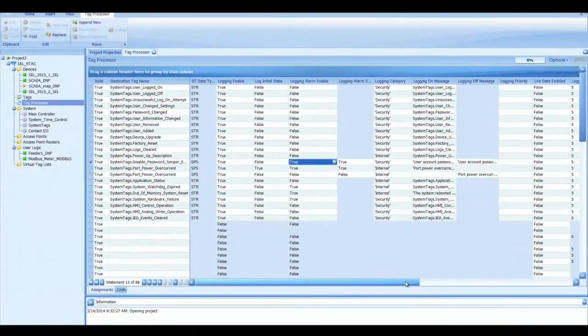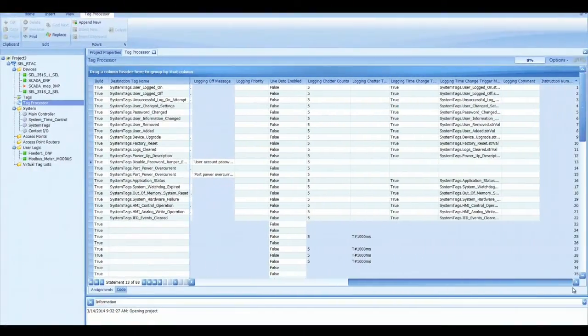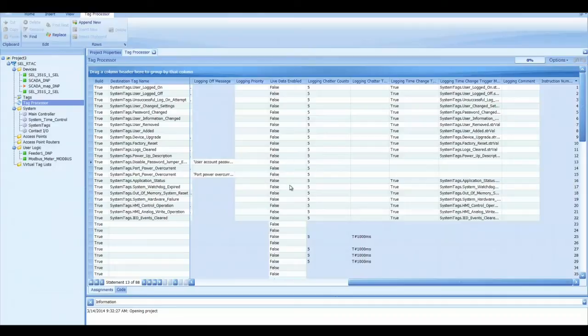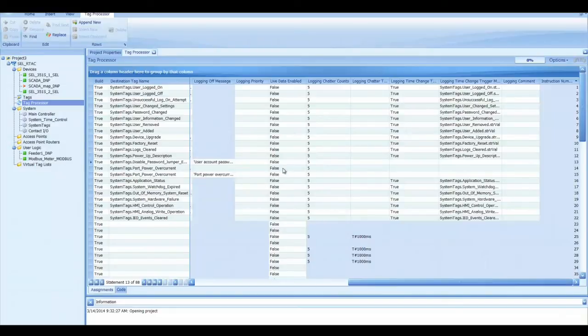Let's scroll over here. Logging priority, that's just a string that you can make up and then you can sort by that priority later. Live data enable is a really cool feature. Any tag that you have configured in the destination tag name, if you turn the live data enable set to true, then it will display that live data on the RTAC web interface.